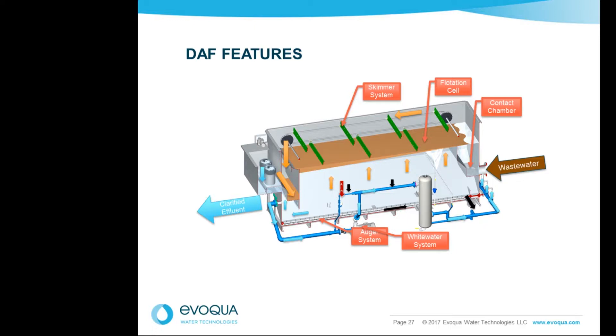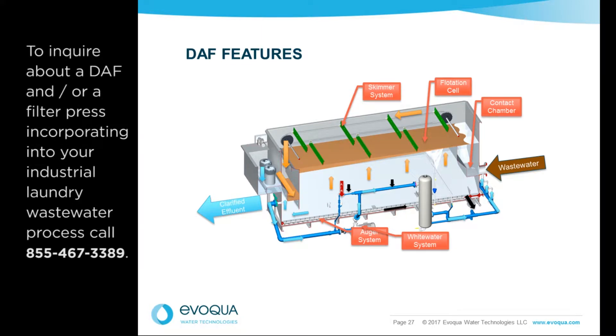All DAF systems have a means of introducing air into water — basically it's forced into solution with the water and released in the form of fine bubbles into the wastewater stream. Because of the white color imparted by the fine bubbles, we call this a white water system. Illustrated here is a recycle white water system that uses the clarified effluent exiting the DAF as the solution stream. That white water, generated by the pump and air injection, is introduced into the contact chamber where it makes contact with the influent solids.